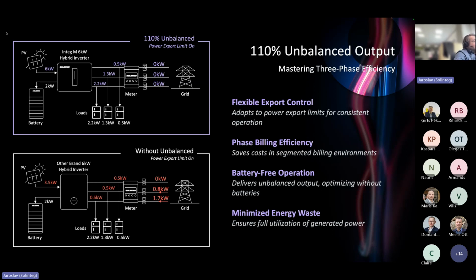And you see on phase 1 you have a consumption of 0.5 kilowatts. On phase 2, you have a consumption of 1.3 kilowatts, and on phase 3, you have a consumption of 2.2 kilowatts, and the production of the PV is 6 kilowatts. You see you cover all these consumptions, and you are exporting zero to the grid and taking no energy from the grid, and you are saving 2 kilowatts to the battery.